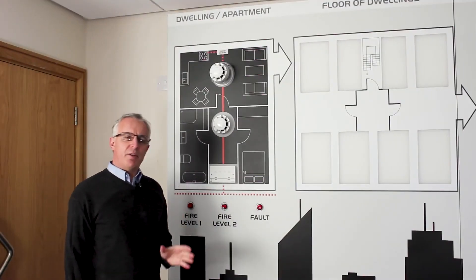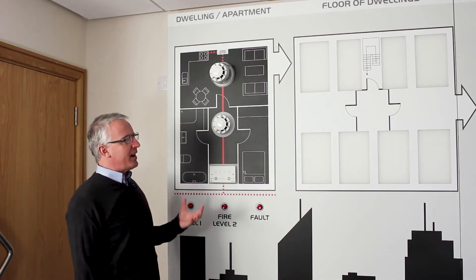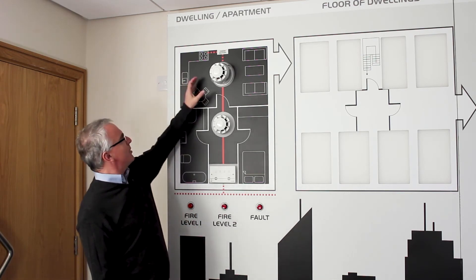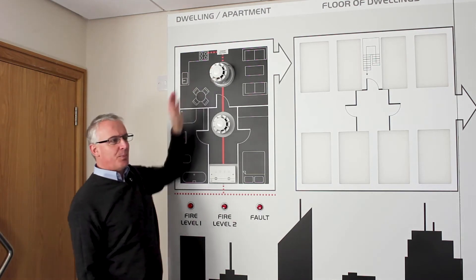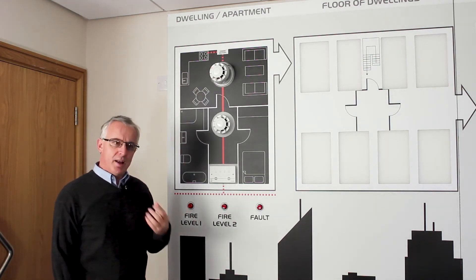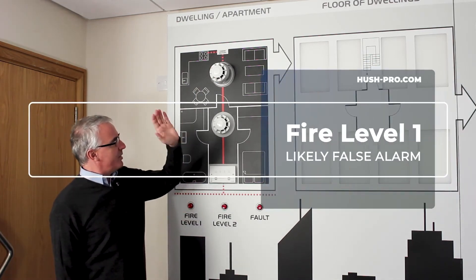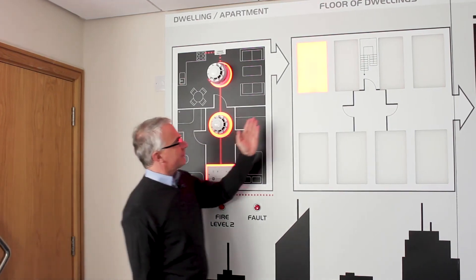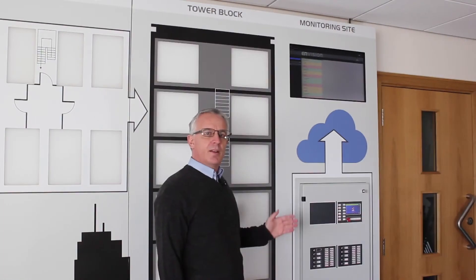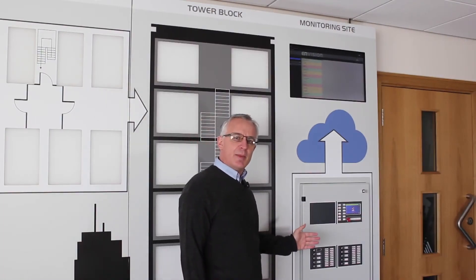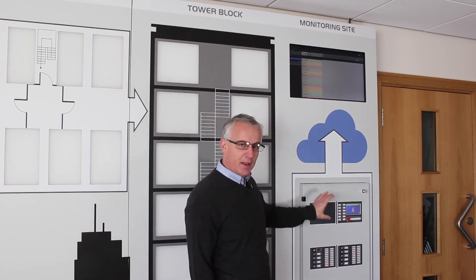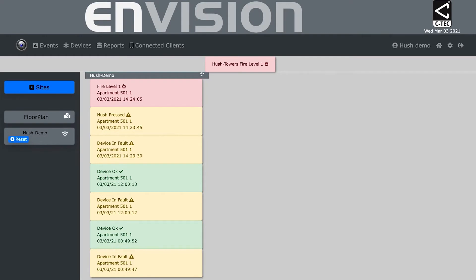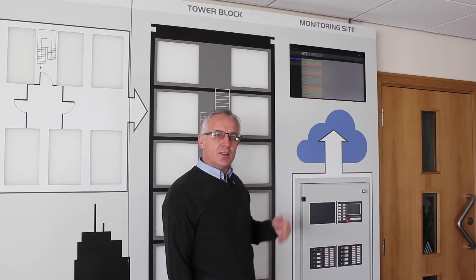With Hush Pro we have also got the fire level 1 and fire level 2 alarm scenarios. Now fire level 1 as we discussed before is potentially a false alarm. Maybe the toast has been burnt in the kitchen and the optical element of the multi-sensor in the open plan lounge area has picked that up. That will flag a fire level 1 alarm which will be reported on this particular dwelling on this particular floor. Okay as fire level 1 is typically and likely to be an unwanted or false alarm it isn't reported on the ZFP's panel display although it is logged at the panel but it is reported off-site via the cloud-based monitoring software. Once the false alarm, if it is a false alarm has been cleared the system will reset as normal.